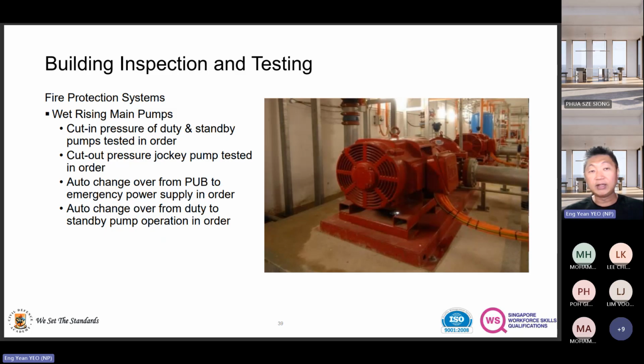Right, everyone get ready to fight, meaning get ready to fight any fire. So the pressure that is needed is 180. When the pressure gauges give me different readings, some show 180, some show 150, then yes, you tell your story: something is wrong. But if both pressure gauges tell me 150, then there's nothing wrong, meaning someone has adjusted the cutout pressure of the jockey pump. And this can only be rectified by your service provider.